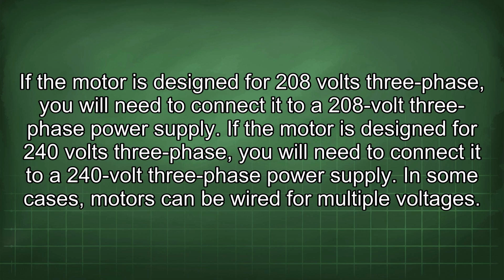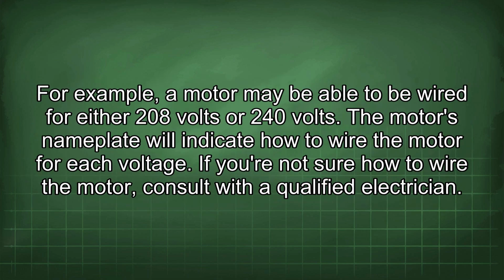In some cases, motors can be wired for multiple voltages. For example, a motor may be able to be wired for either 208 volts or 240 volts. The motor's nameplate will indicate how to wire the motor for each voltage. If you are not sure how to wire the motor, consult with a qualified electrician.